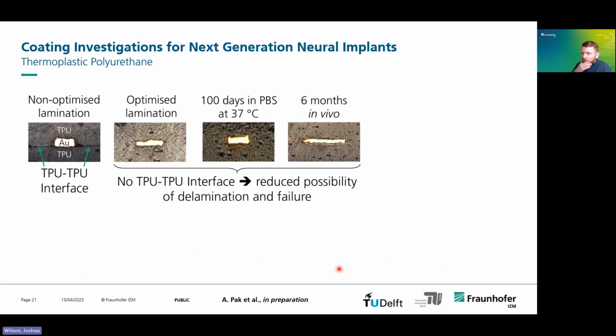Now, if we take a look at this polyurethane, if we start to build a device, then we will have a TPU, a thermoplastic polyurethane substrate, and we will do some lithography processing with some gold metallization, and then we laminate a second layer of TPU on top. When you build up these multi-layer structures, you have a lot of interfaces. There's a TPU-TPU interface, there's a TPU gold interface, and all of these interfaces are potential points of failure. Anywhere the water can get in and travel towards the electronics to start corrosion, or even just delaminate the two different polymer films to separate them, this is going to destroy your device.